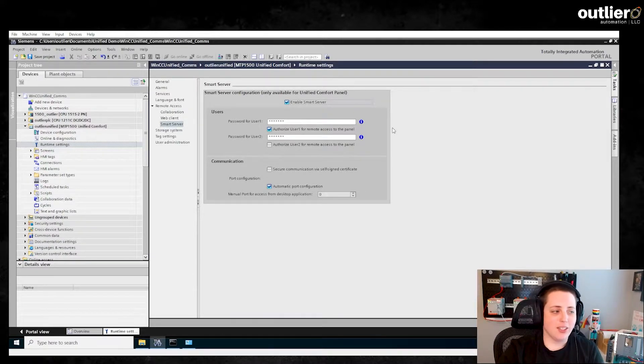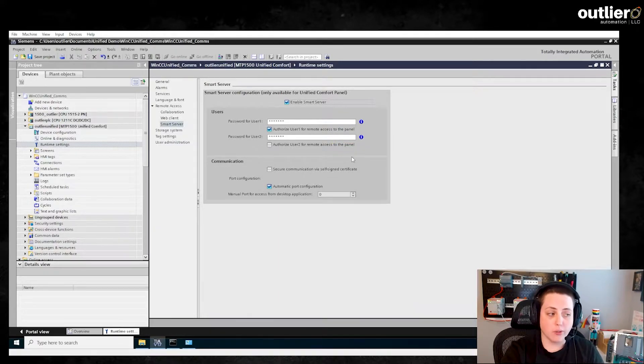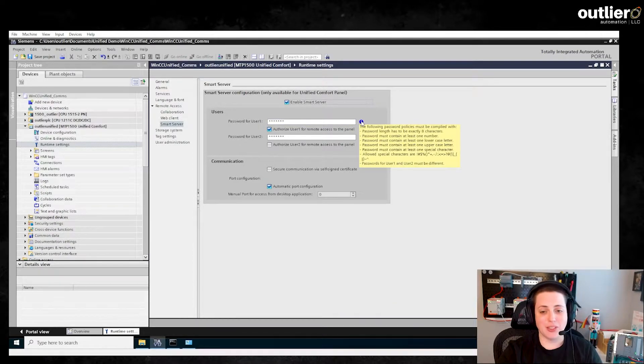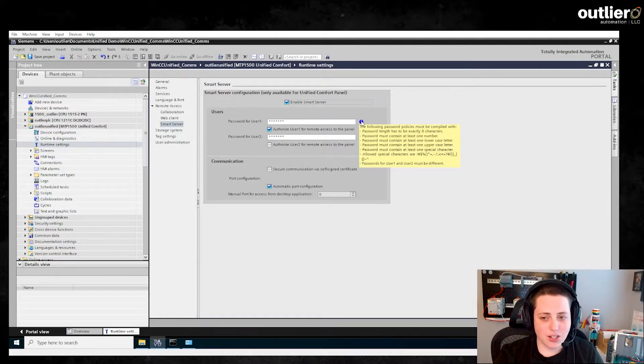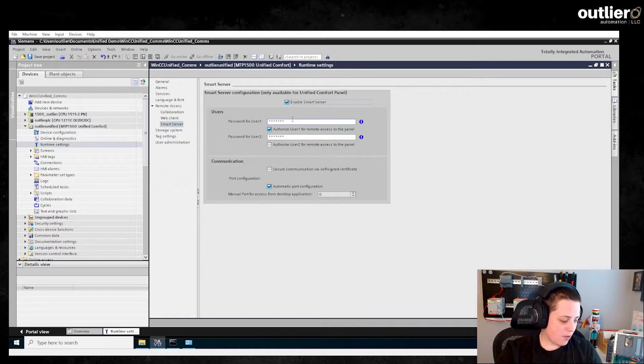Like most things with TIA Portal version 17, you have some security settings which are enabled now for almost anything that could remotely connect to a device, since someone could hack it. So you have two different passwords here for different users. Make sure you pick a password that follows the complex password scheme — it has to be exactly eight characters and a combination of upper, lower, special, and number characters.